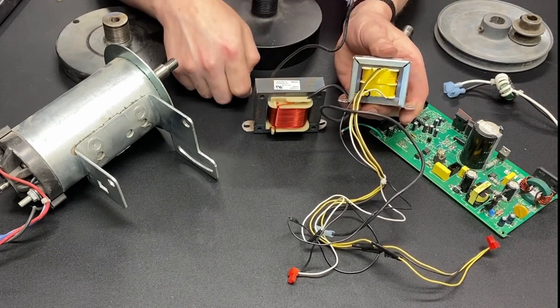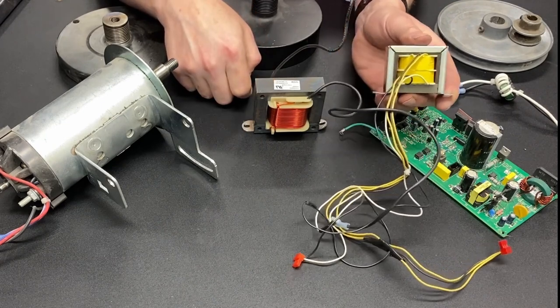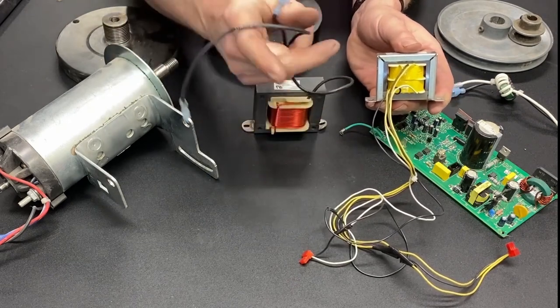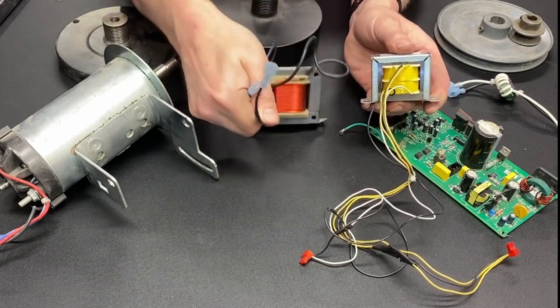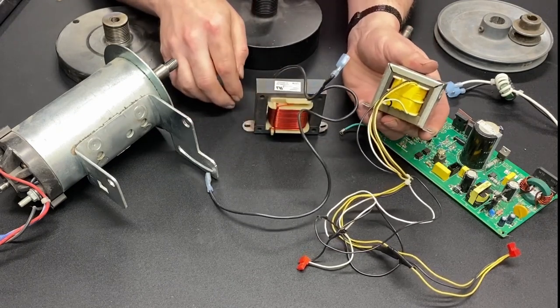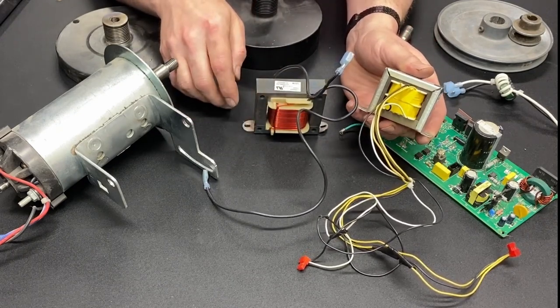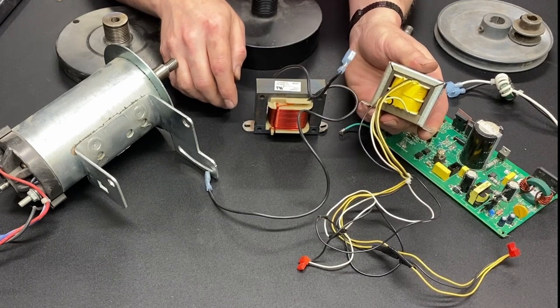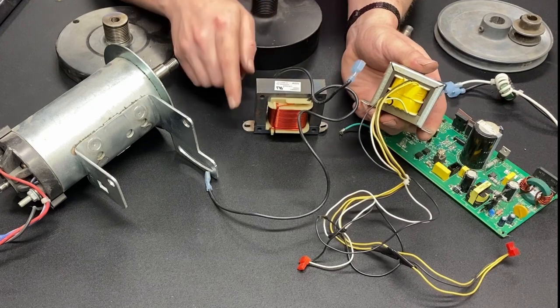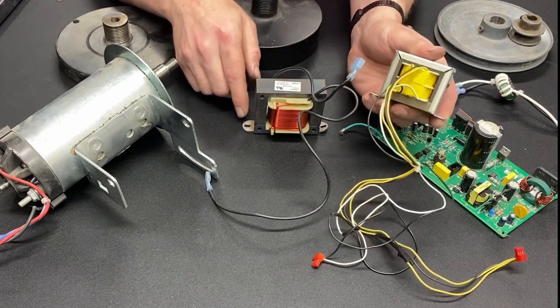And, the only way that you can tell the two apart is to count the wires. A motor choke will have two. Power flows in on one side and out on the other. A transformer will have anywhere from three to six to eight wires in it. So, two wires is a choke. Three or more wires is a transformer.